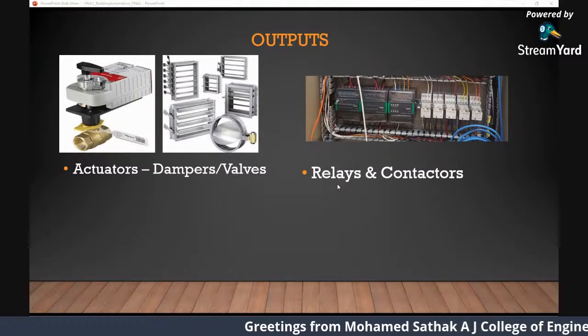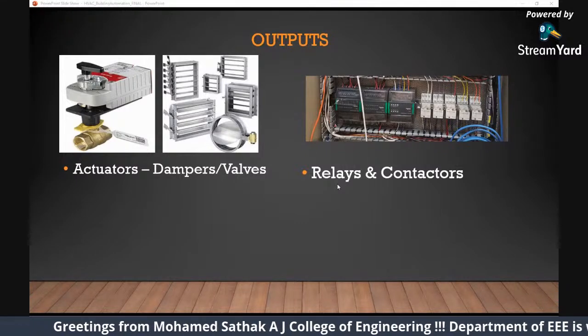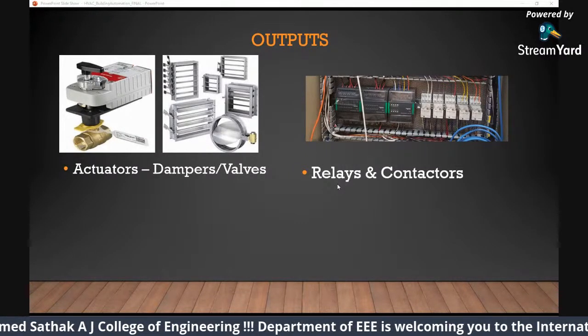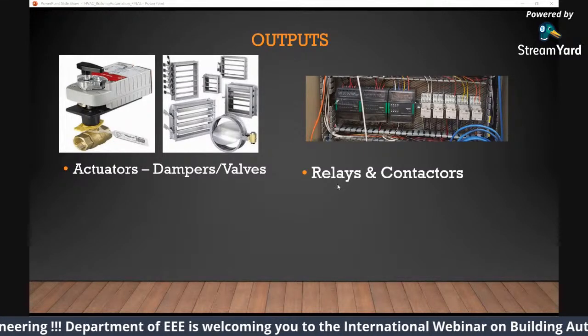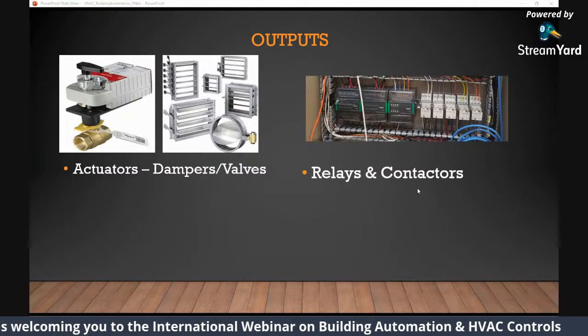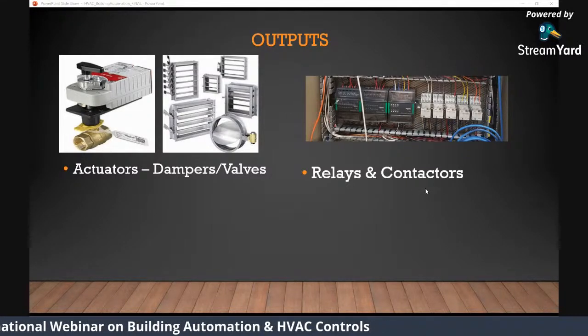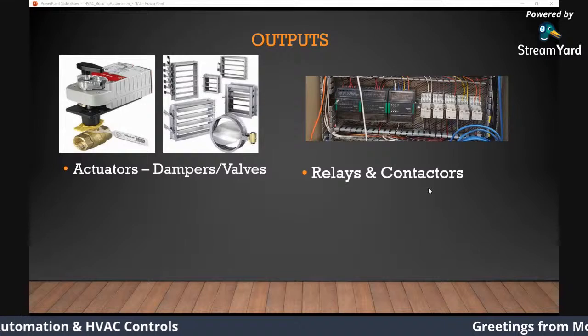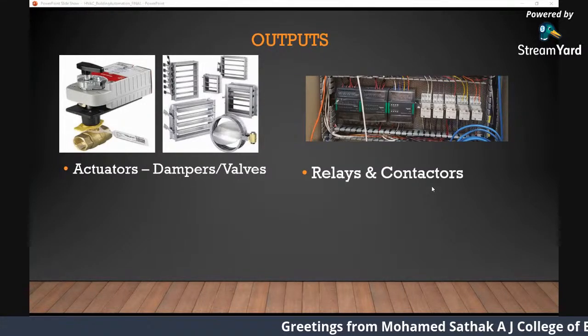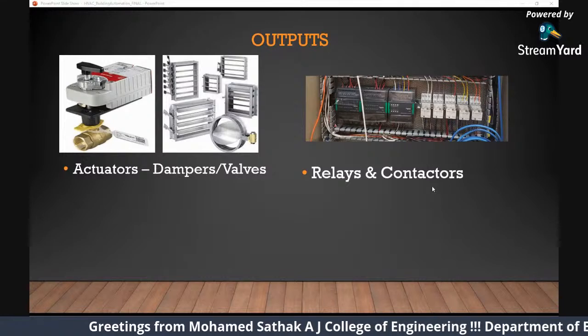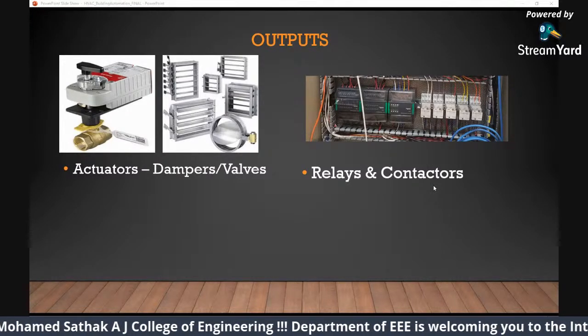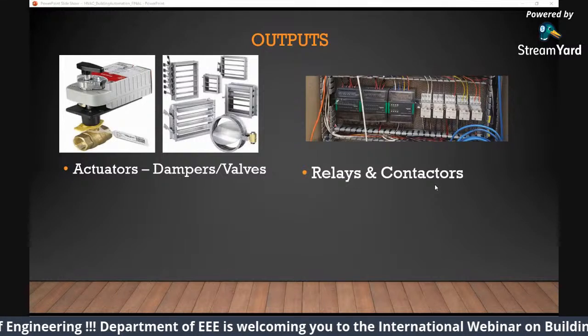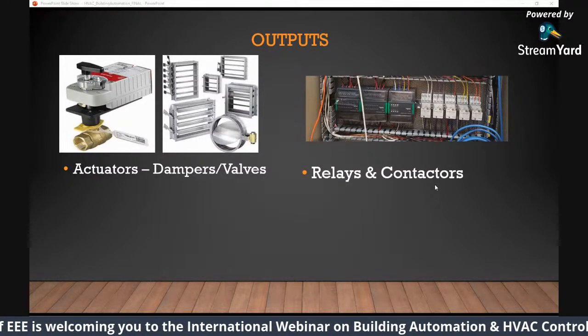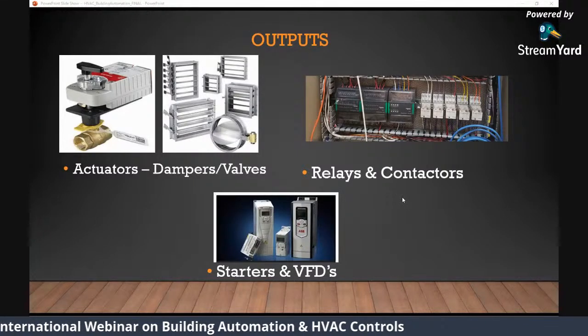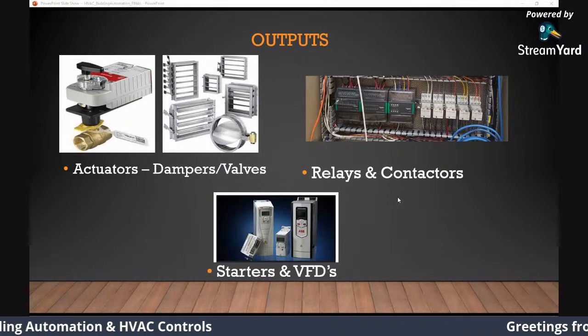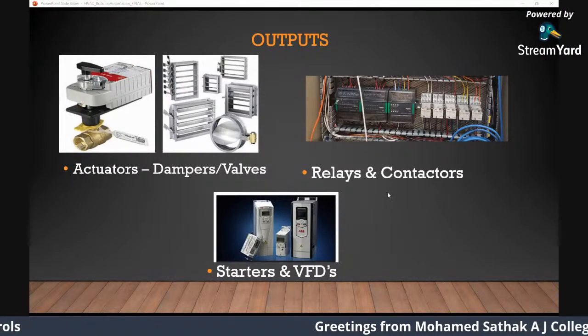Okay, so your controllers, let's say you want to turn on the fan. Let's say you have switches, right? Instead of turning on the fan manually, your controller senses the temperature and turns on the fan through relays and contactors. So again, as I said, there are three important parts in building automation: your input, your controller, your output. Controller is your DDC or your PLC or any simple microprocessor. Your inputs are your temperature sensor, flow sensor, pressure sensor, and your humidity sensor, whatever. It senses, it monitors, it sends input to your controller. Your controller will send output to your output devices, which are actuators, relays, contactors, and VFDs. Actuators for your dampers and valves, relays and contactors for your pumps and fans, fans for AHUs, pumps for your chillers and boilers.